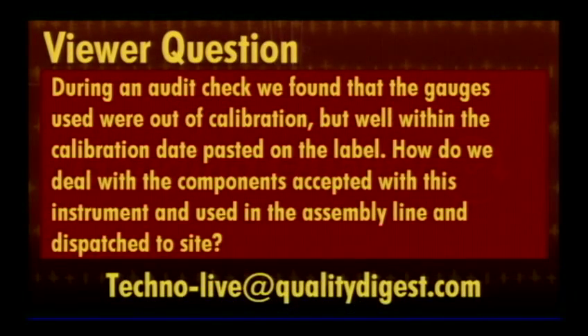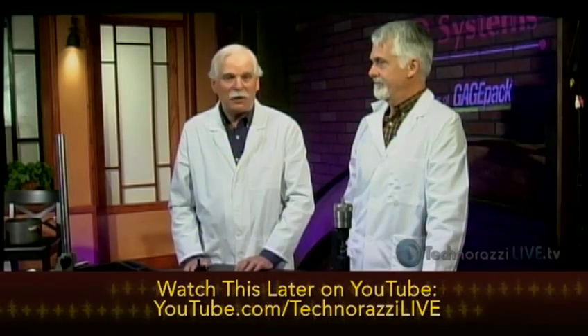During an audit check, we found that the gauges used were out of calibration, but well within the calibration date posted on the label. How do we deal with the components accepted with this instrument and used in the assembly line and dispatched to a site? They have a problem. The calibration due date means nothing in this case. If they know the gauge is bad, those parts would have to be rechecked. It's a common occurrence. Somebody dropped the gauge, now parts are hanging off. It doesn't matter what the date on the calibration tag says, they would have to redo it.